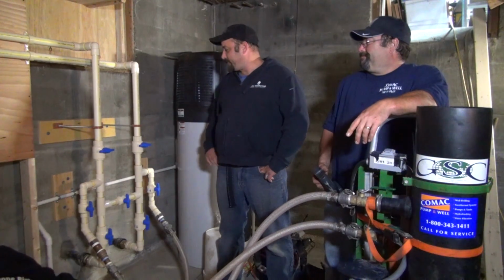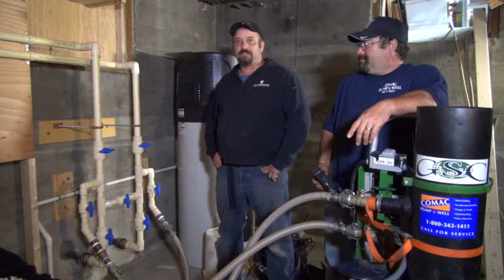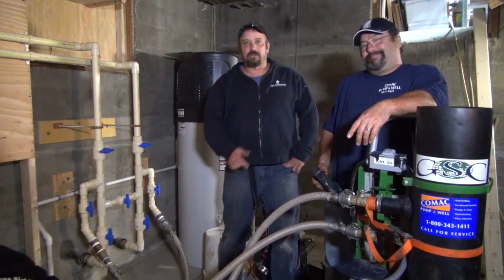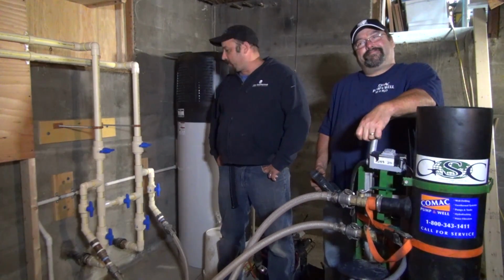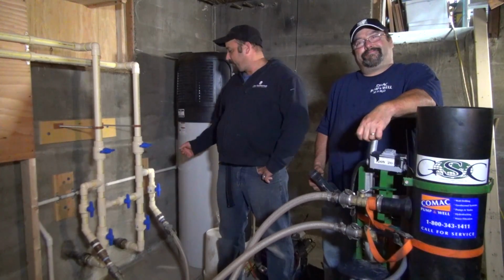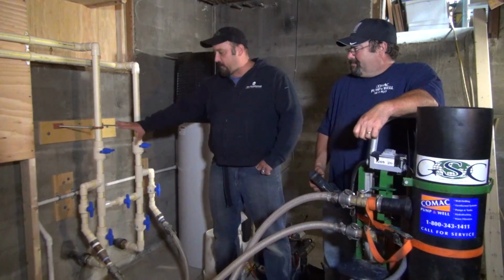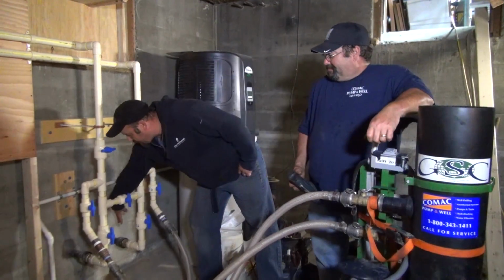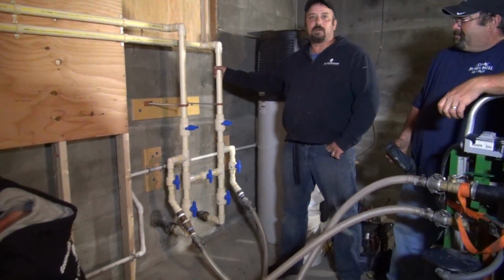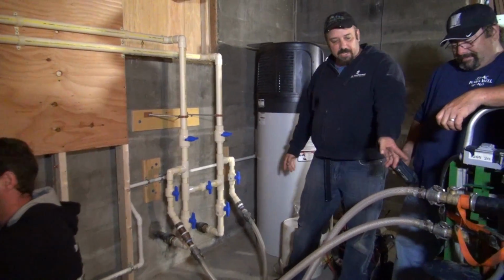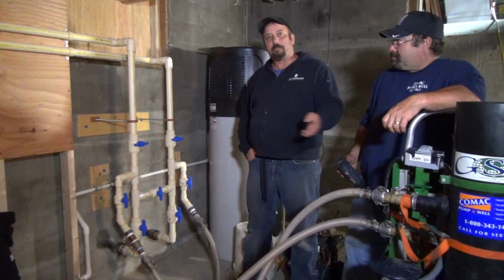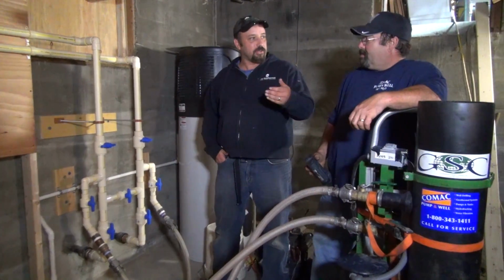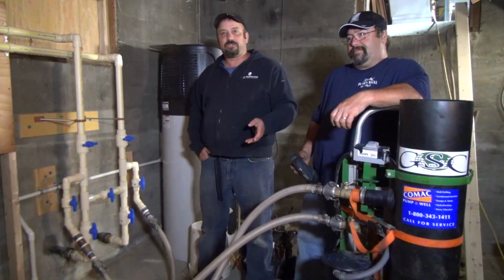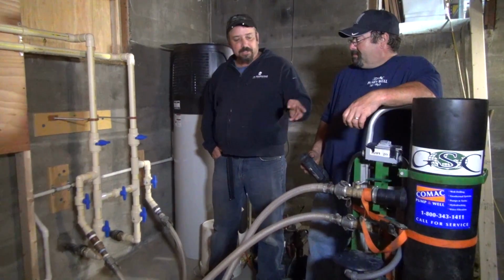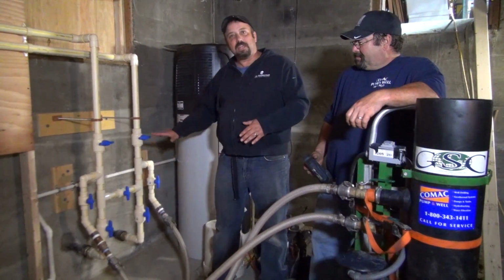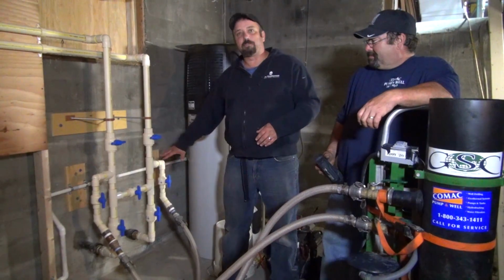Here we are a couple days later. We're starting to see things getting connected to the geothermal system. I'm here along with Bill from Comac Well and Pump, who's working with us doing the closed loop horizontal system here. Basically, we now have the loop field from the outside connected to an indoor purging manifold. Bill here has what we call a pump cart, which is what you use to pump water into that loop field, as well as a mixed glycol solution. In this particular case, it's a product called CP Therm, an environmentally safe product, and that is all going to be inserted into the loop field through this purging station.